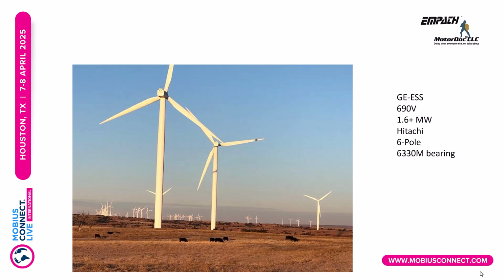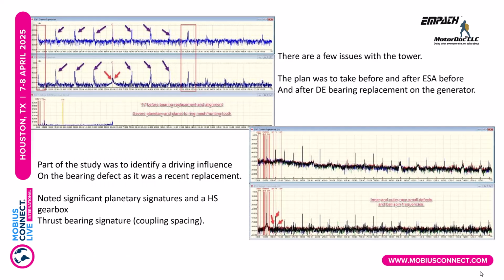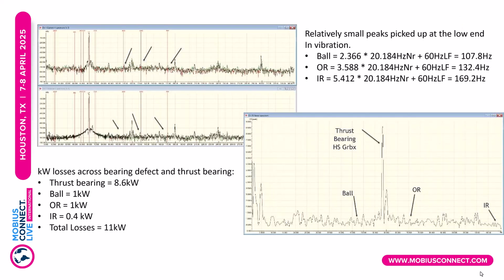So, 1.6 megawatt Hitachi 6-pole, 6330M bearing. There were other issues with the gearbox. That's what all those pink arrows go to. But it was noticed right after they put everything together that some peaks showed up related to bearings. So they took a look in there, and as a matter of fact, not only did very, very small peaks show up on the bearings on the machine that were just perceptible as well in vibration, but there was a sizable peak in the high-speed gearbox thrust bearing, which the vibration transducers did not see.